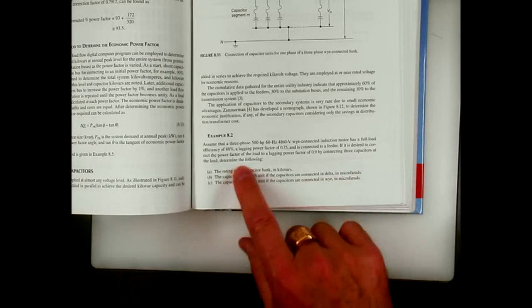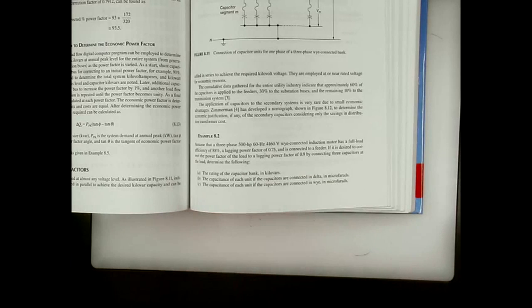It is desired to correct the power factor of the load to a lagging power factor of 0.9 by connecting capacitors at the load. Determine the following. Now why are we specifying 0.9? That's right, remember that's the practice -- the normal practice for utilities is not to correct to 100%, but to 90%.